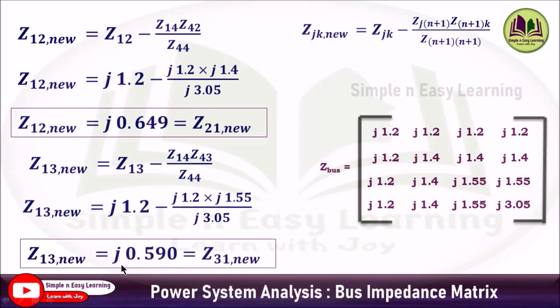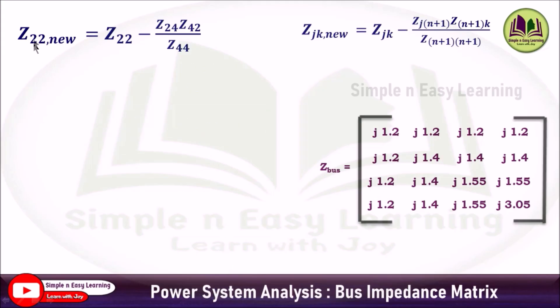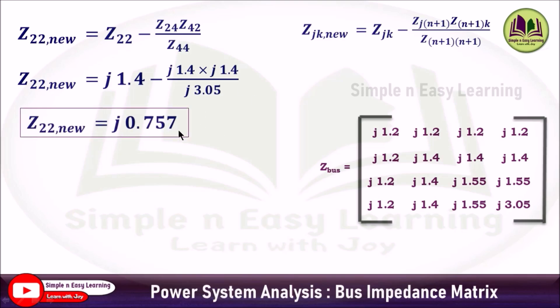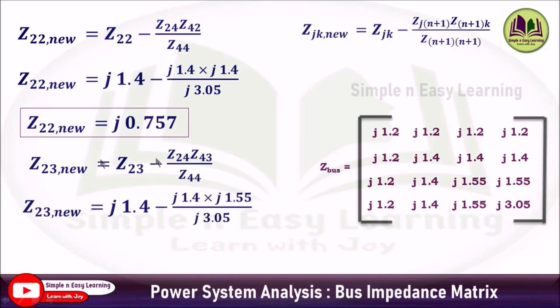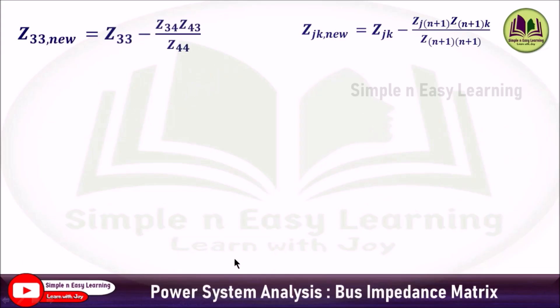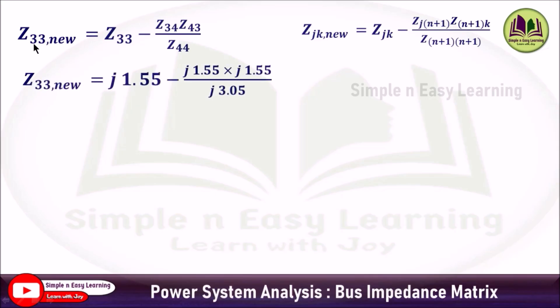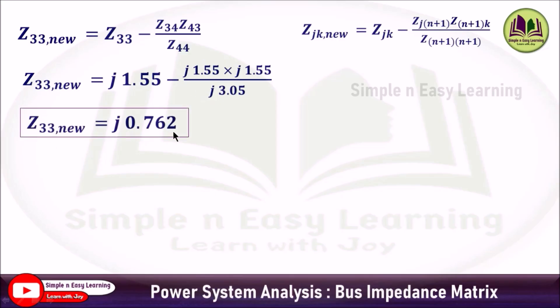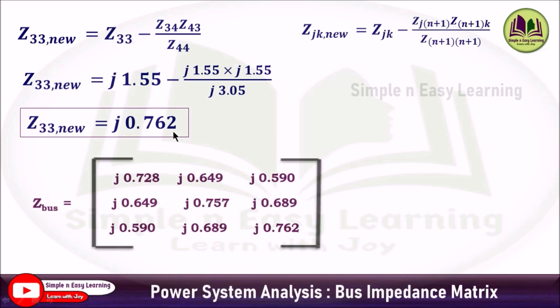Substituting the values from the matrix: Z13 = j0.590, and that equals Z31. Similarly, Z22 (j=2, k=2) equals j0.757. Z23 (j=2, k=3) gives j0.689, which equals Z32. Finally, Z33 (j=3, k=3) gives j0.762. So all nine parameters are calculated.